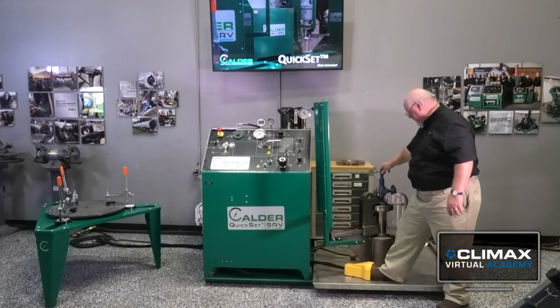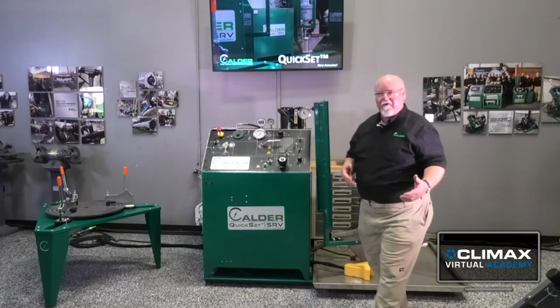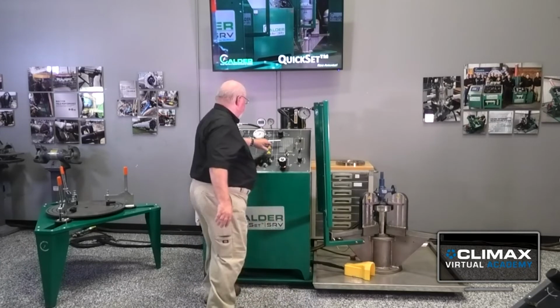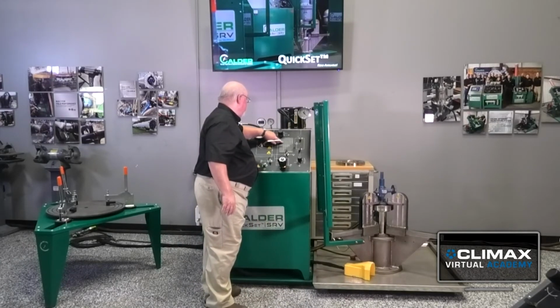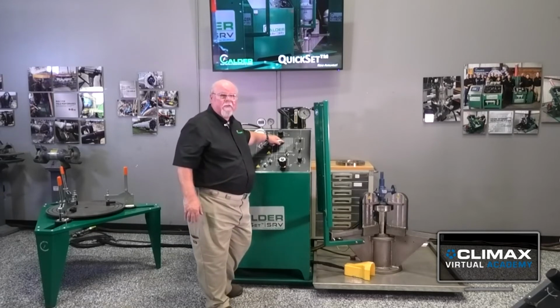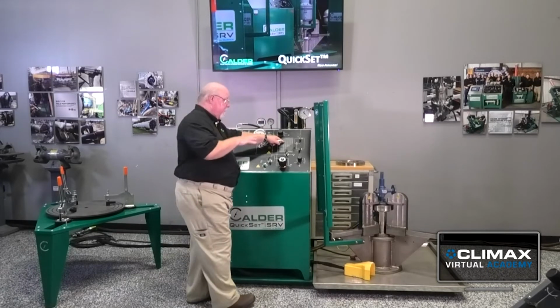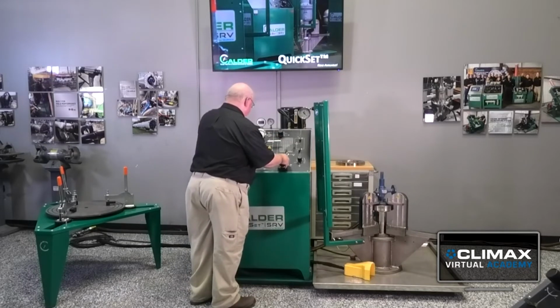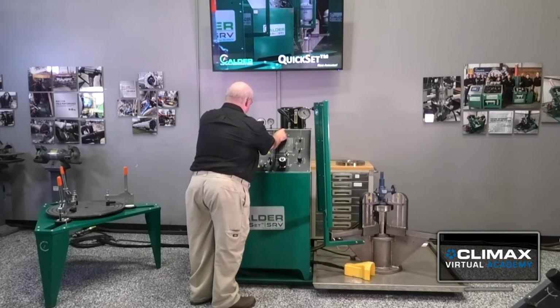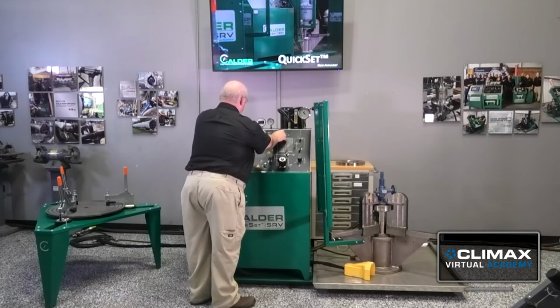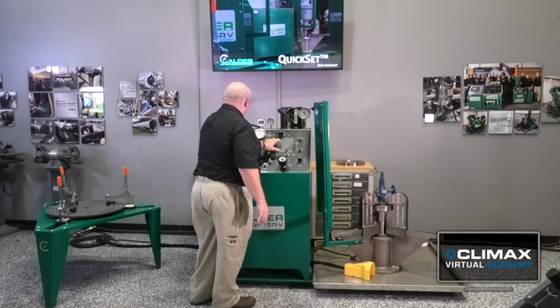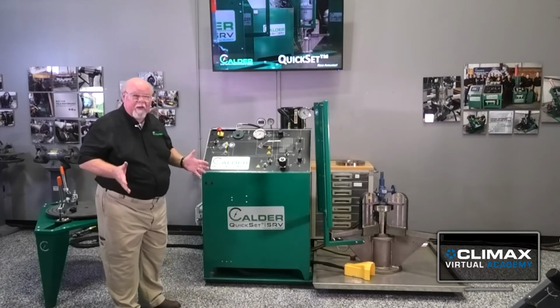This particular valve is set at 400 psi, and as you can feel right now, that's rigid. With 400 psi, I know it's a 1-inch inlet valve, so I can come to my chart here and go to 1 inch. Really all I need is a 100 psi clamping pressure to hold the valve for this test. I'm sitting at less than 100, so I'm going to adjust my regulator to provide the 100 psi clamping force. And so there we sit. The valve's clamped in place and it's ready to be tested.